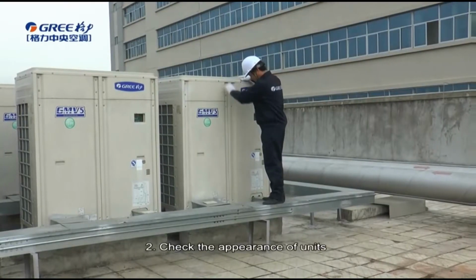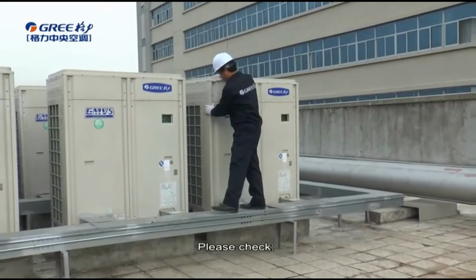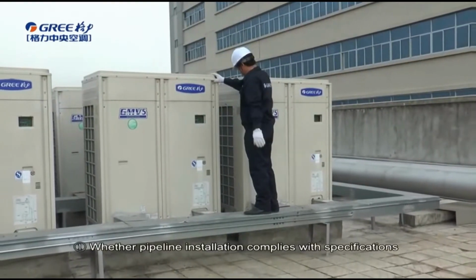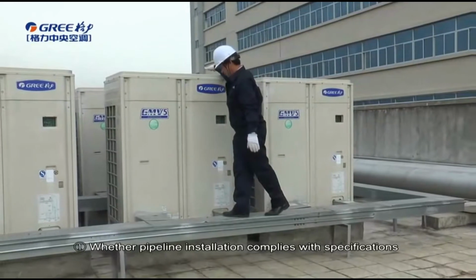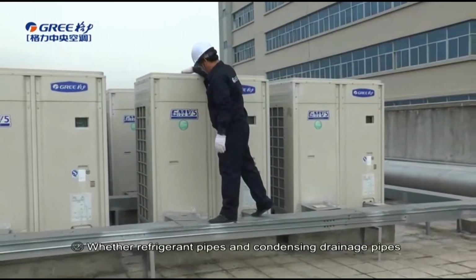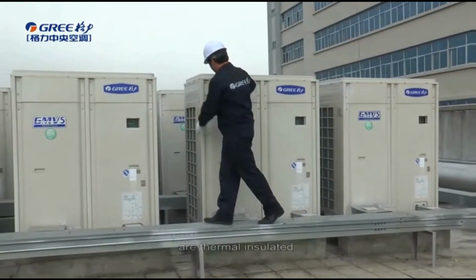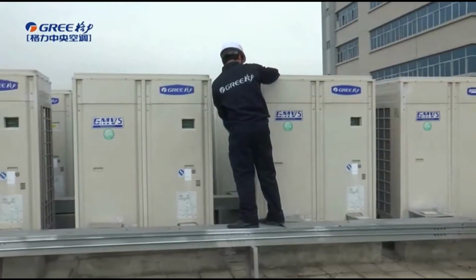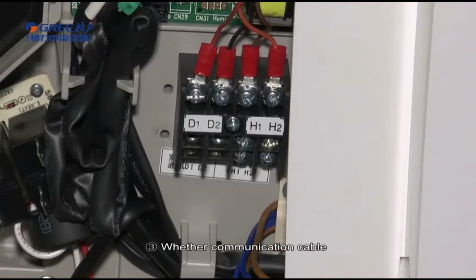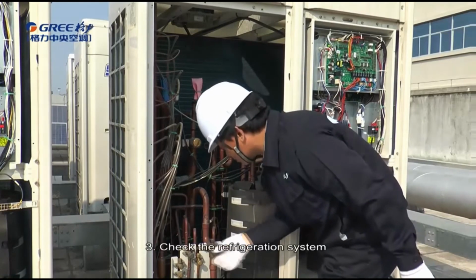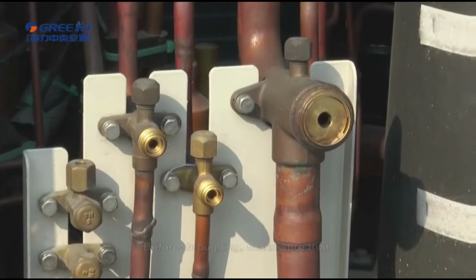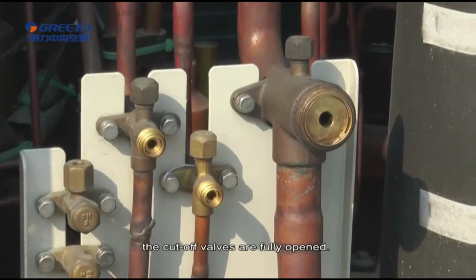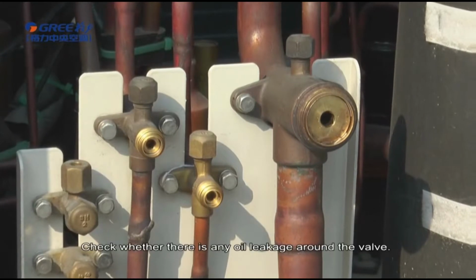Check the appearance of the units. Please check whether pipeline installation complies with specifications, whether refrigerant pipes and condensing drainage pipes are thermally insulated, whether communication cable complies with installation regulations, etc. Check the refrigeration system. Before debugging, make sure that the cutoff valves are fully opened. Check whether there is any oil leakage around the valve.